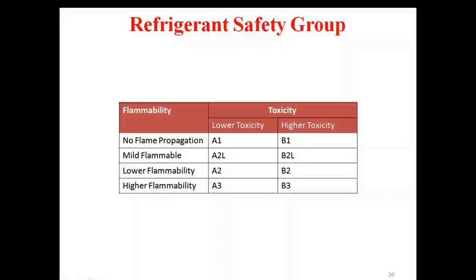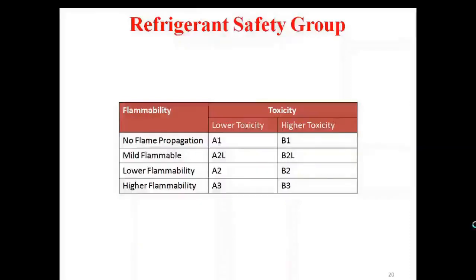Next is the refrigerant safety group. This covers flammability and toxicity. Moving from 1 to 2 to 3 in flammability represents moving from no flame propagation towards higher flammability. In toxicity, A represents lower toxicity and B represents higher toxicity. So A1 represents no flame propagation and lower toxicity. For an ideal refrigerant, we want it to be in safety group A1.